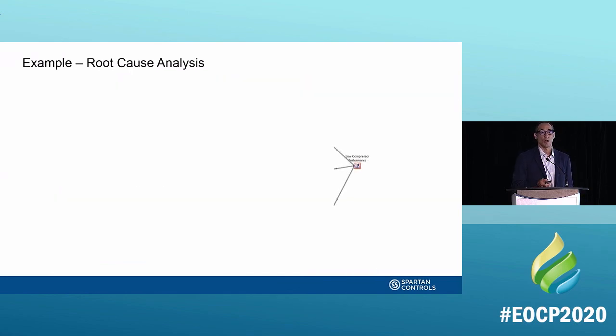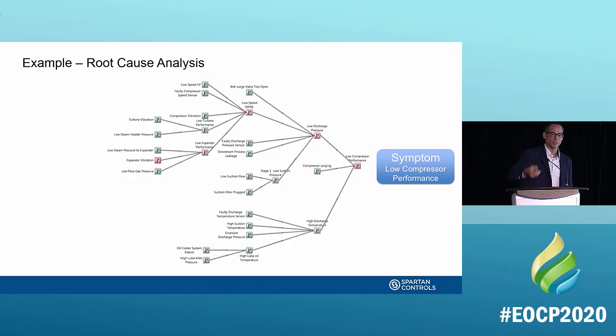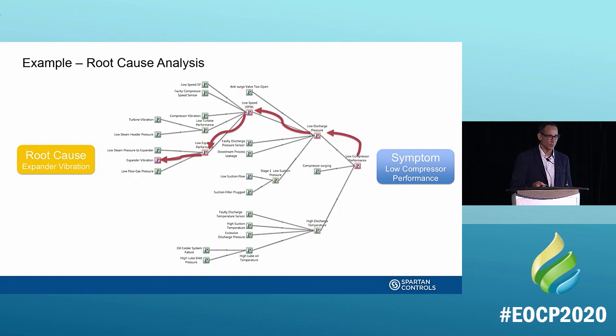As an example of prescriptive analytics, consider root cause analysis for low compressor performance. Low compressor performance can be caused by low discharge pressure or high discharge temperature, and each of those sub-conditions can be caused by further upstream conditions. By building a set of rules using that data, we can trace the low compressor performance back through the chain — low discharge pressure caused by low speed, caused by the next condition — all the way to the actual root cause: expander vibration. That's much more specific than a traditional check engine light where you have no idea what it means.